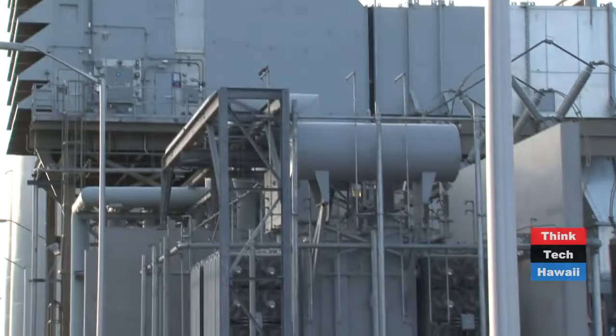Air comes in there and comes down into the turbine. The way the air comes in is there's actually a set of 14 rows of fan blades—turbine blades—that when the turbine's spinning actually sucks the air in. So the way we start it up is there's a 2,000 horsepower electric motor tied to it. We start that up and that brings it up to speed, starts bringing in the air, and at a certain point we can put in fuel, and then we don't need the electric motor anymore.